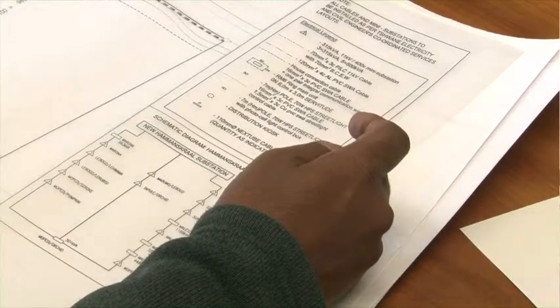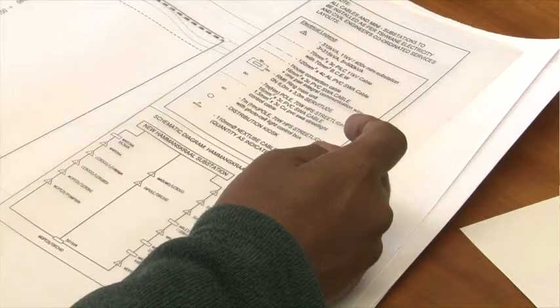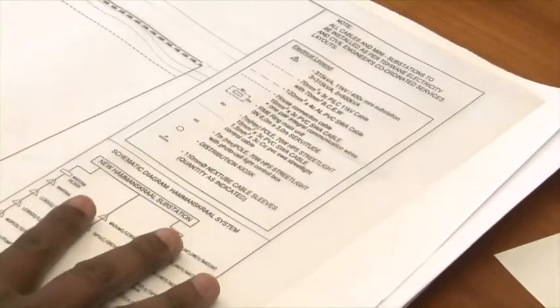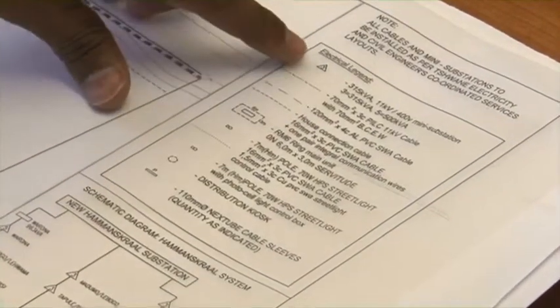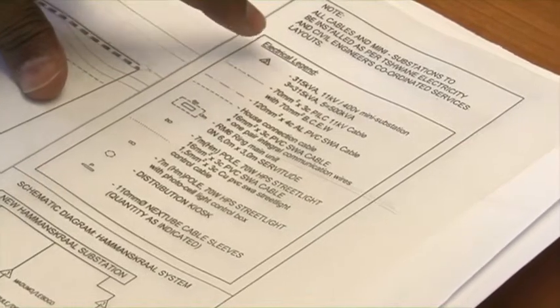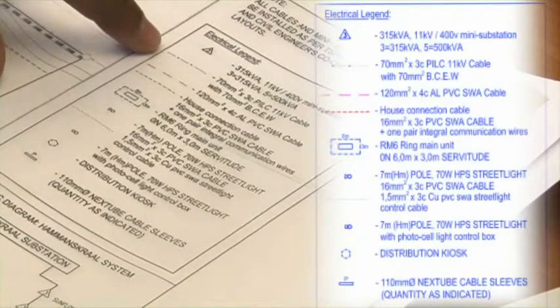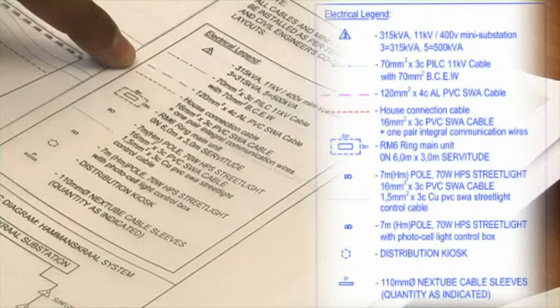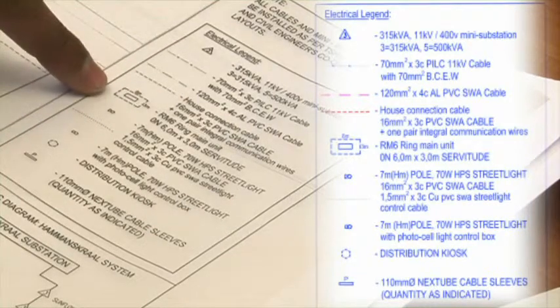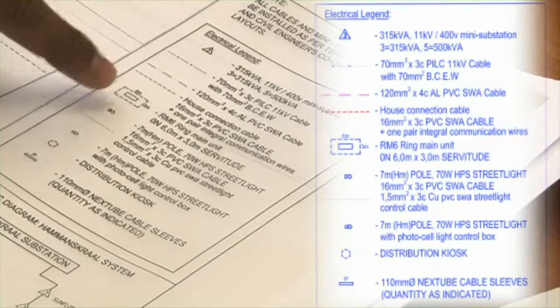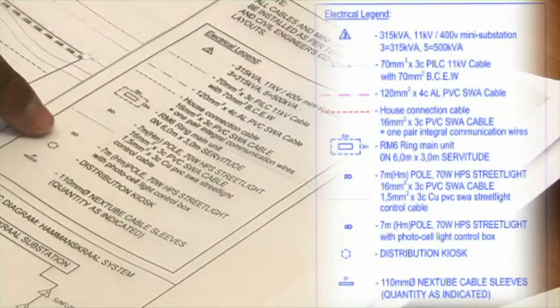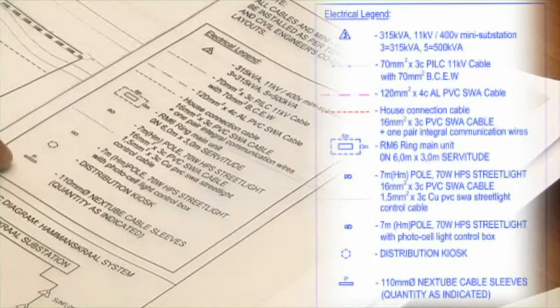Now, the medium voltage system, briefly, in this particular layout, what does it look like from a schematic perspective? If you look at the legend here, it gives you the various elements that service the township from an 11 kV perspective. We've got miniature substations, 70 square millimeter 11 kV cables, 120 square millimeter LV cables, house connections, ring main units which are switching points, street lighting, LV distribution boxes, and sleeves.